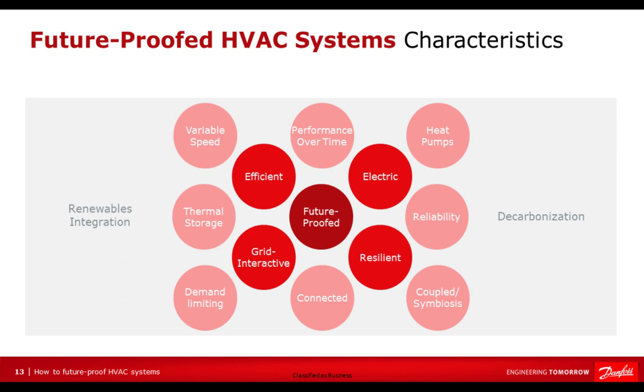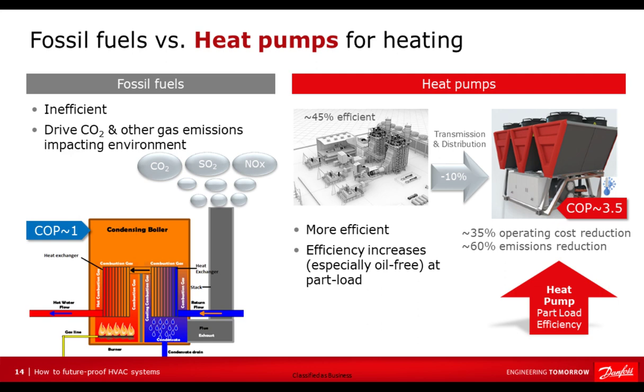Tied to that grid-interactive factor is demand limiting. For grid-interactive efficient buildings, the number one factor for HVAC systems is the ability to respond to the utility signal to demand limit those components. That in turn ties to variable speed, and the ability of a variable speed HVAC system to exactly respond to that demand limiting signal while closely matching the thermal load at the same time.